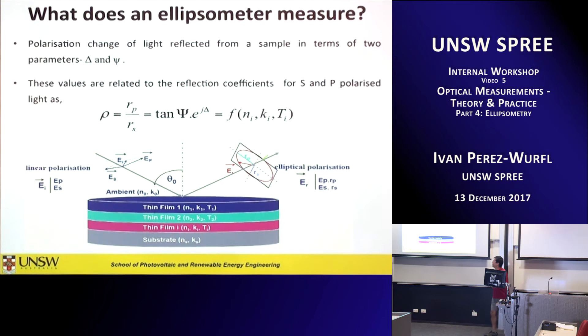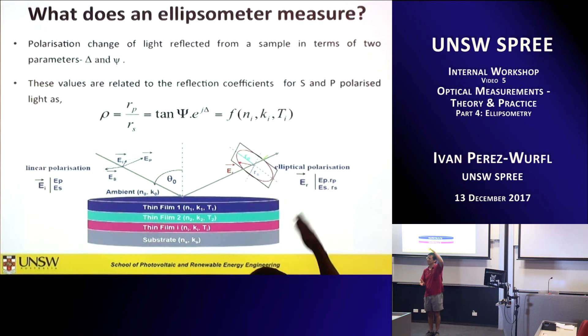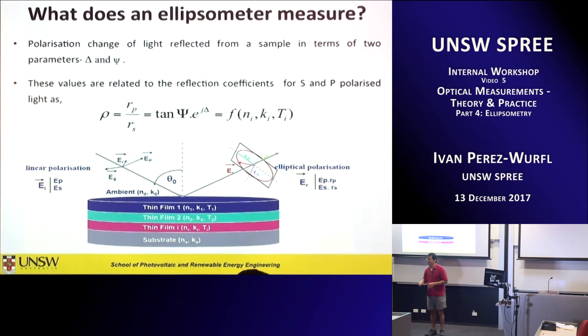When you look at the ellipsometry equation, you realize the power of it in terms of stability and reliability — it's a ratio. So if you have noise, the noise cancels out. If the intensity of the light fluctuates, unless S-polarization and P-polarization are changing at different rates — which isn't the case with an incandescent lamp source — everything cancels out. You don't need a double beam. You don't need to calibrate anything, because we're not measuring reflection; we're measuring the ratio and interpreting from there.